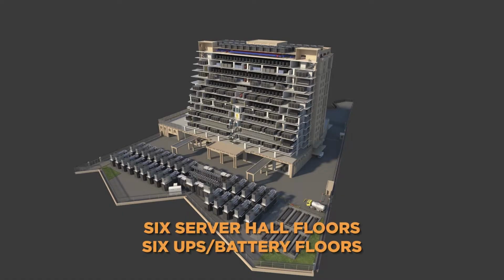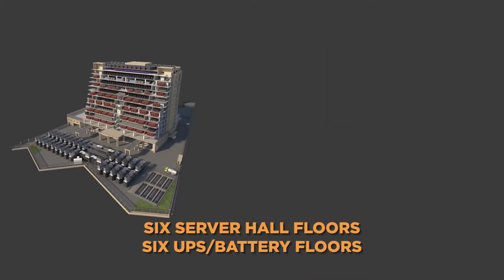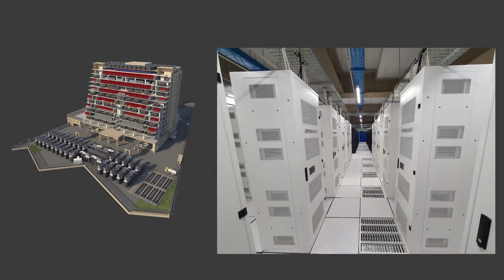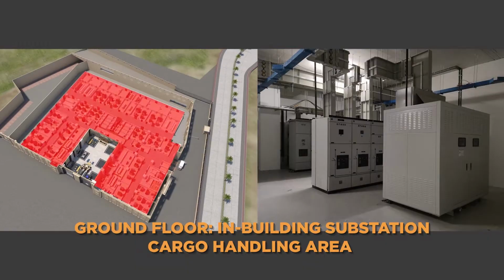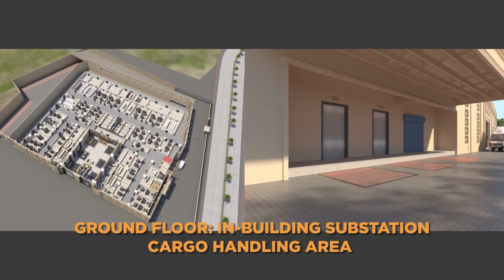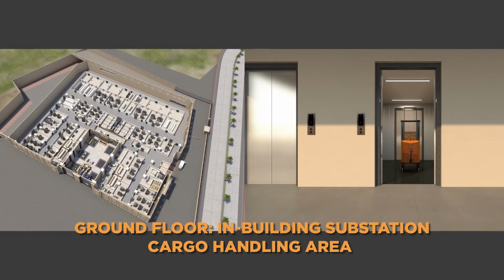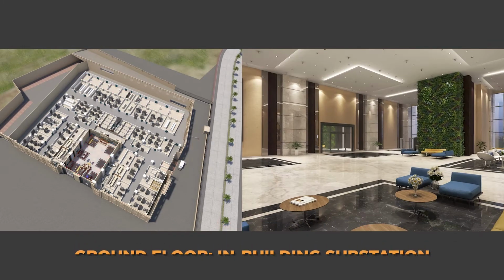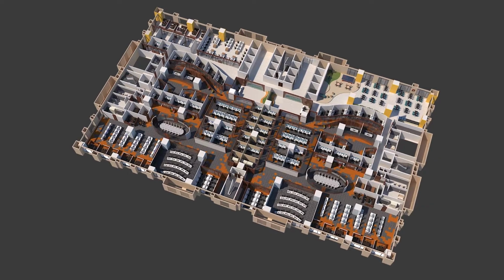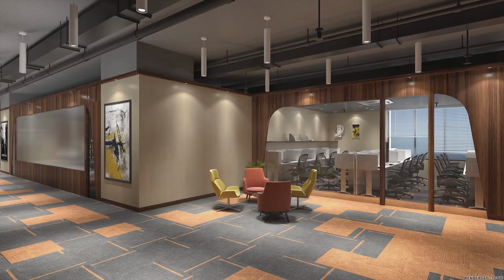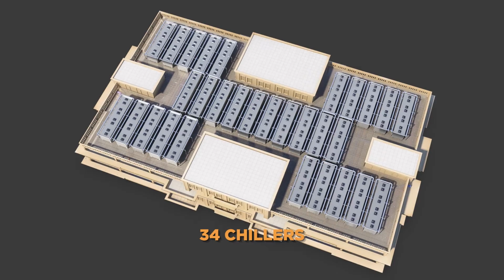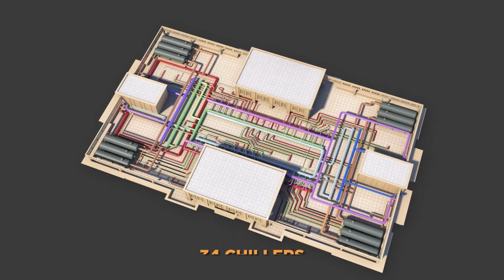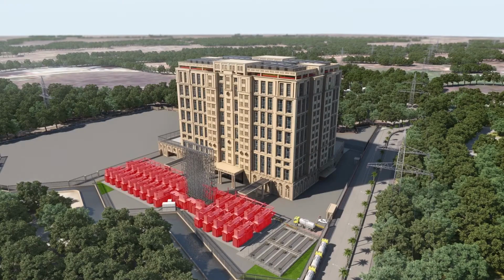Yotta NM1 is a ground plus 14-story building. Even numbered floors are dedicated server halls, and odd-numbered floors are dedicated UPS and battery rooms. The ground floor includes in-building substation, dedicated cargo handling area, scissor lifts, cargo elevators, storage rooms, and a podium with visitor reception along with meeting rooms. The building has an entire floor dedicated to customer seating. The terrace of the building has chillers installed on an elevated platform and chilled water distribution plant below the platform. The backup diesel generators are placed outside the building on an elevated platform with underground fuel tanks adjacent to the same.